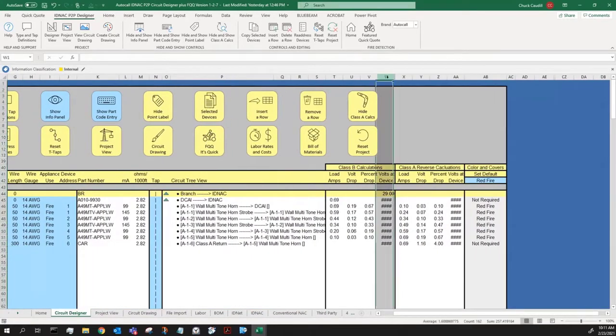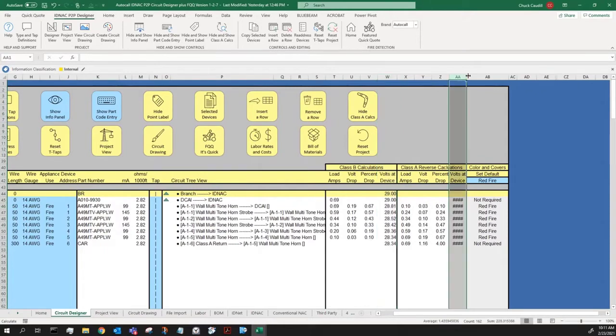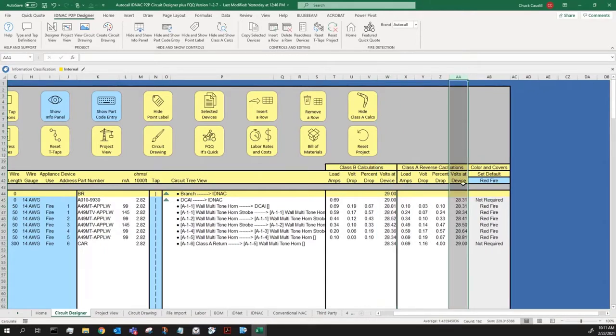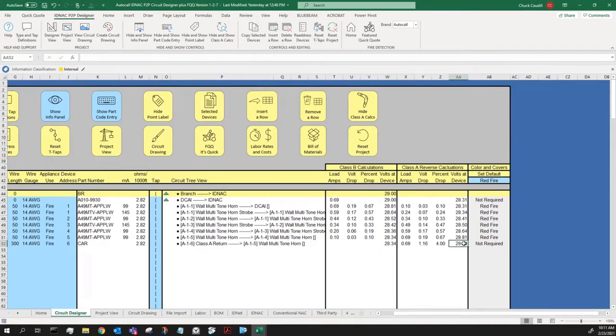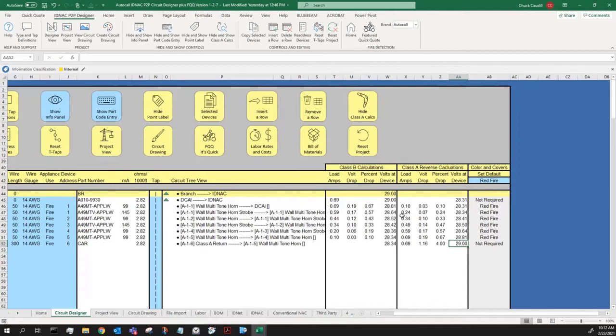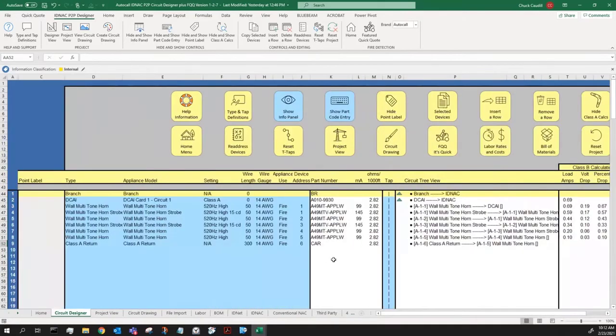I'll open up this column so you can see the voltages. If you double tap on the line there, it opens it up. And I started with 29 volts from one side, and as I got further away from the panel, the voltage decreased. The Class A return starts from the other way and starts at 29 volts, and it drops down the further I get away from the panel. If I get a break in the wire between this device and this one, everything will still work. You'll get a Class A communication trouble, but all the devices are functional.